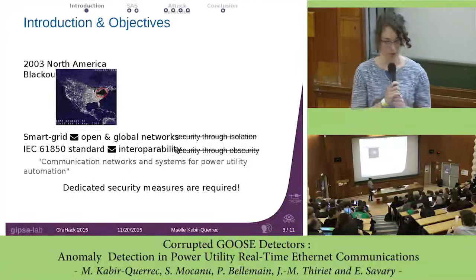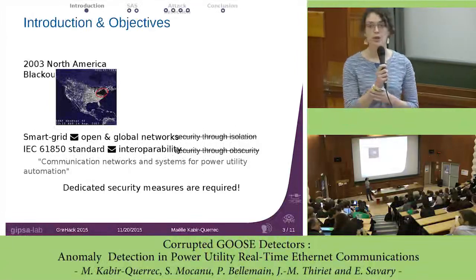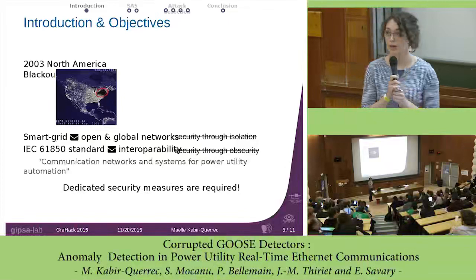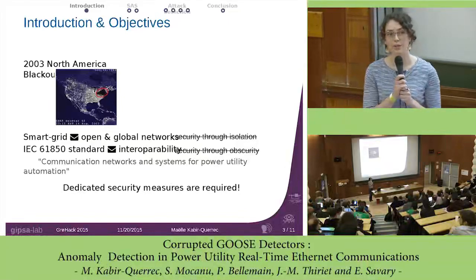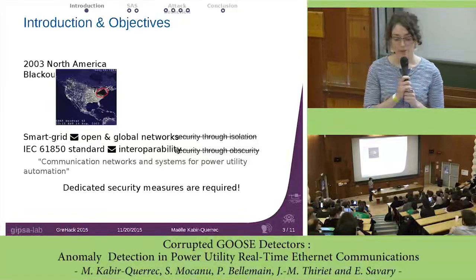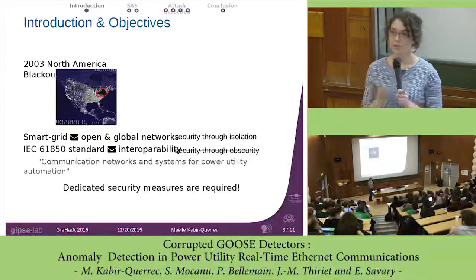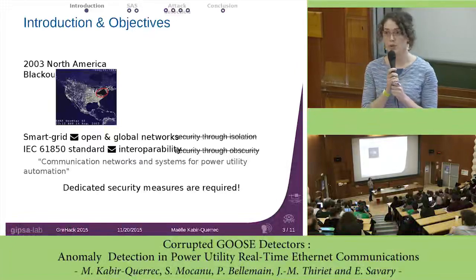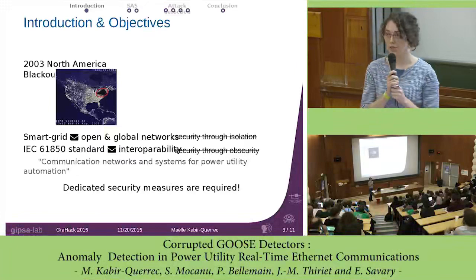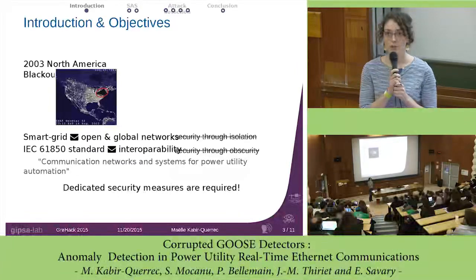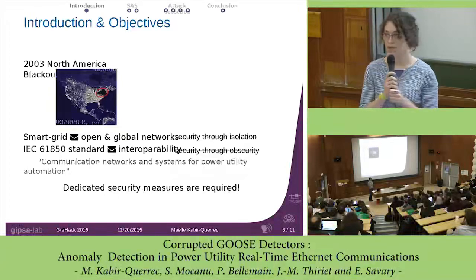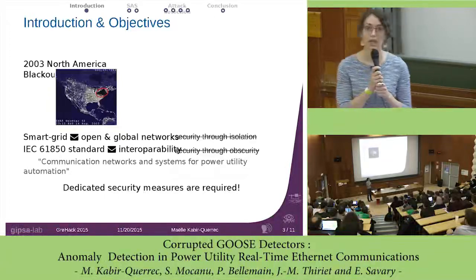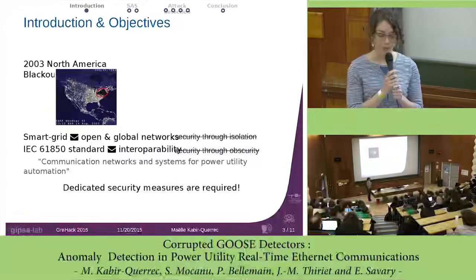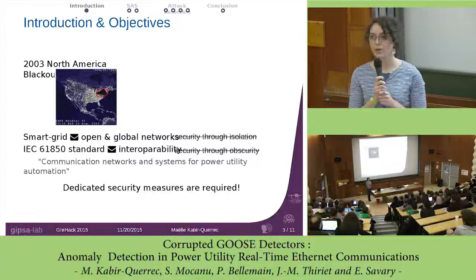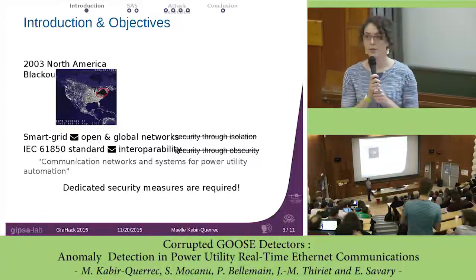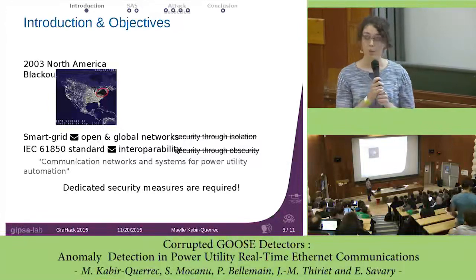I'm starting with an example. This is a picture of the 2003 North America Great Blackout. It was due to a defective state estimator. This state estimator was restarted, but the monitoring tool associated was not restarted. Added to that, there was a cyber bug which blocked the alarm system for about 1 hour, depriving operators of any state information for 1 hour. This resulted in a cascading failure and finally in this great blackout. This was not a malicious attack, it was an accident.